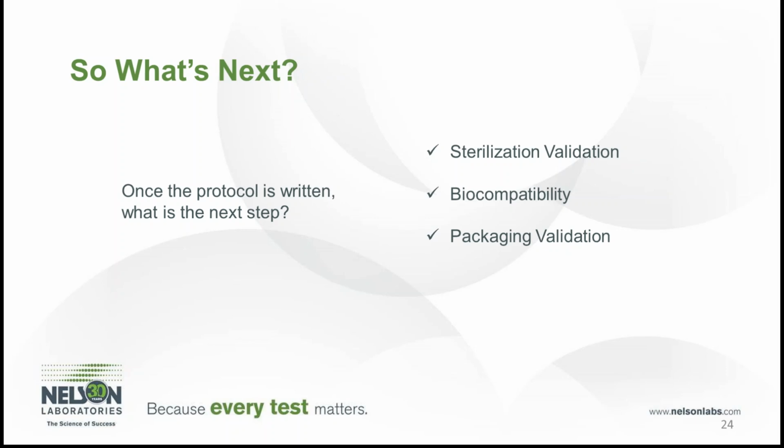Sterilization validation is done first because you want to make sure you're using validated sterilization parameters for your packaging and biocompatibility testing. Once all the testing has been completed, the data needs to be reviewed to determine whether or not the results passed. This is usually accomplished by compiling the data from all the different phases, the sterilization, biocomp, and the package validation, and comparing the results to the sample acceptance criteria listed in your validation or master protocol.